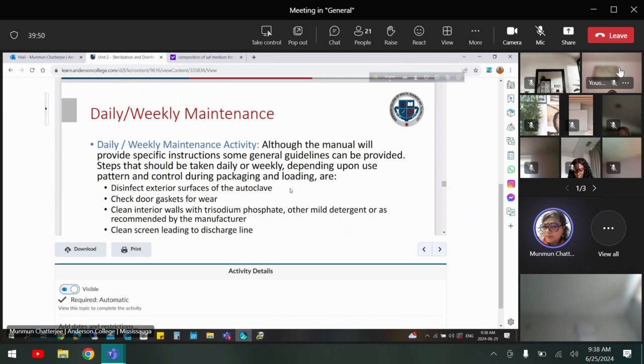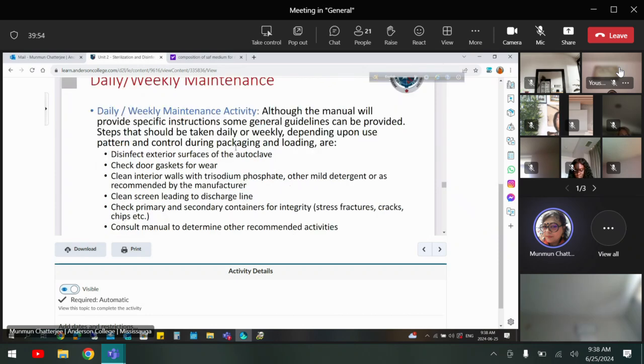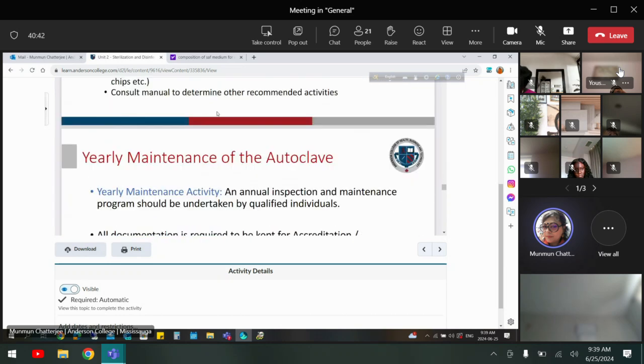Daily or weekly maintenance: each autoclave comes with specific instructions in its manual. But what are some general guidelines? Disinfect the exterior surface of the autoclave. Always check the door gaskets for wear or tear, because the gasket is the main thing. Close the door tightly, like a pressure cooker; we have the gasket ring. Clean interior walls with trisodium phosphate or another mild detergent as recommended by the manufacturer. Clean the screen leading to the discharge line so that you can see it. Check primary and secondary containers for integrity, like stress, fracture, cracks, chips, etc. And consult the manual to determine other recommended activities.